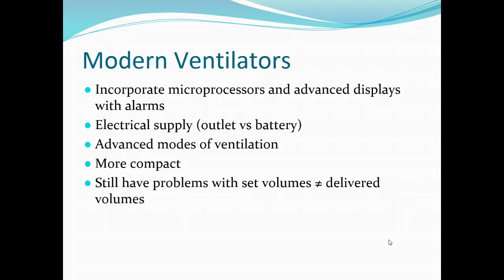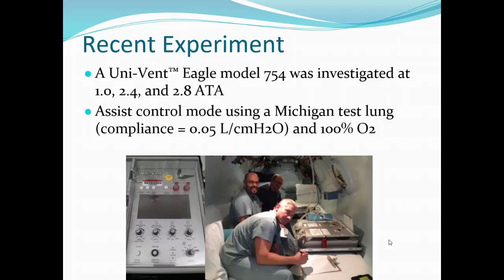And so these are the guys at UCSD. This is Dr. Watucki, he's the program director there, and Dan and Jay Duchnik. They did an experiment using the Univent Eagle model. It's the standard ventilator that they use there. They tested different volumes at different atmospheres: 1, 2.4, and 2.8, or sea level, 45 feet, and 60 feet of seawater. They used the Michigan test lung with a compliance of 0.05, set at 100%.